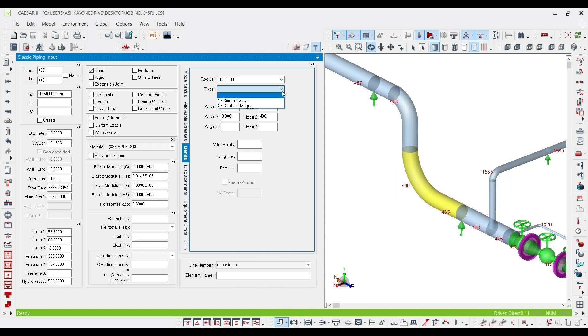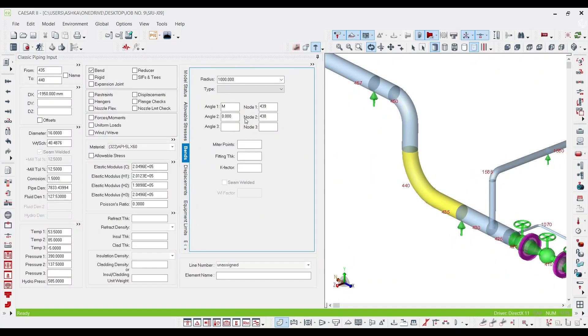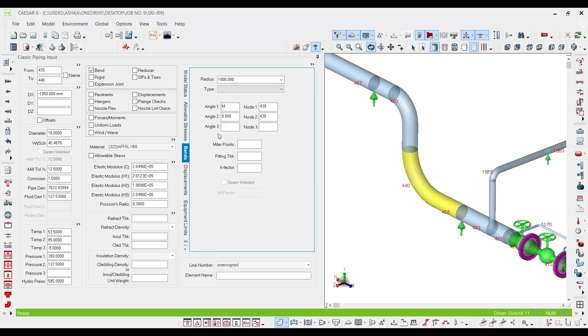In this section, you can change the value of each bend segment by setting a value for that angle. For example, you can break your bend into three sections and for each of them you can add a value for your angle, but you have to consider that the summation of all the angles in 1, 2, 3 must be equal to the final direction change that you're going to have.